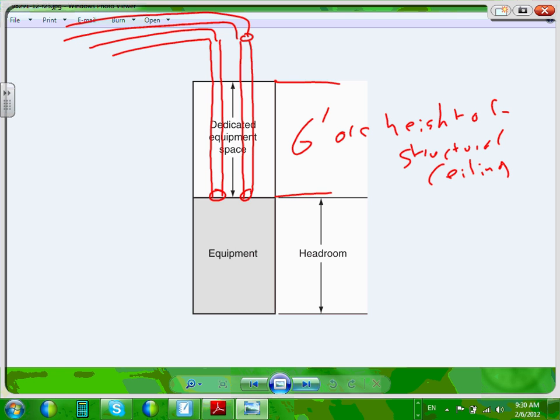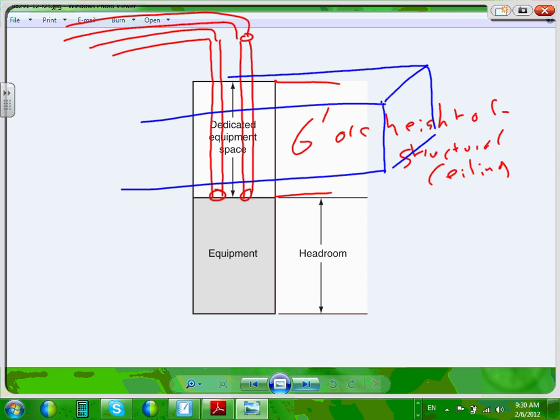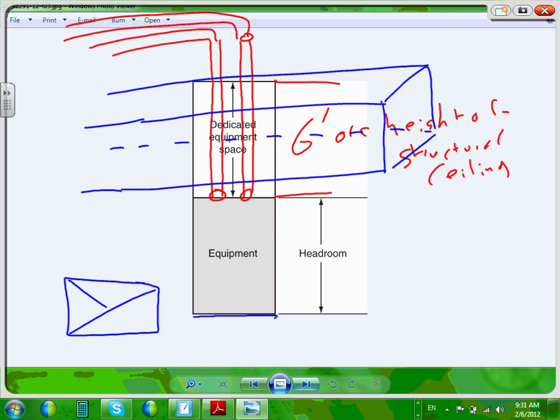But what they don't want you to do, guys, is for a mechanical contractor to come and put a big duct right above the equipment, and good luck trying to move your equipment here, right? So if you see this, and there's a conflict between you and the mechanical, as a project manager, you're going to take this rule, dedicated space for electric equipment. This is above and below the electric equipment, to the depth and the width of the electrical equipment. How deep is this space? If you take a cross-sectional area of this space, you're going to take it to the width and the depth of the electric equipment. So suppose that was 4 feet, and that was 8 feet. So a 4 by 8 space above the switchgear, that's a sacred cow. Don't enter. Dedicated space, not working space. Dedicated for the equipment, working for the people.